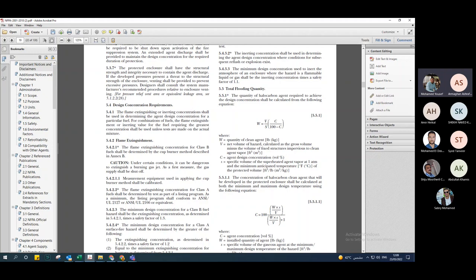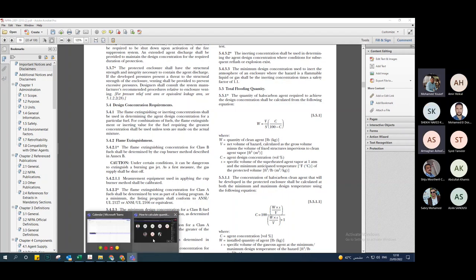The third parameter is S — the specific volume of superheated agent vapor at one atmosphere and the minimum anticipated temperature of the protected volume, in Fahrenheit or degrees centigrade. We will also learn how to calculate S.